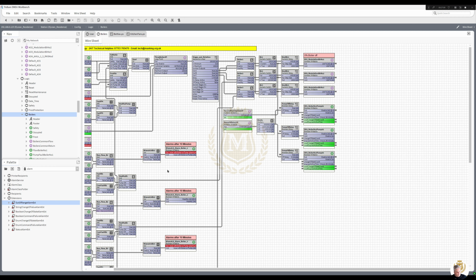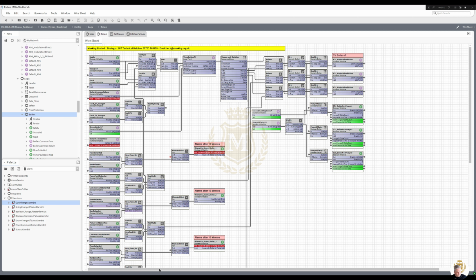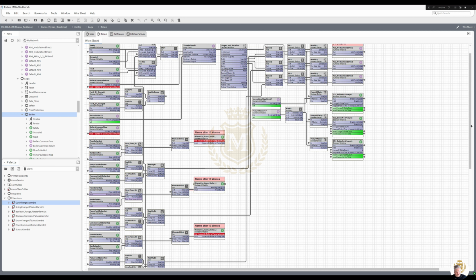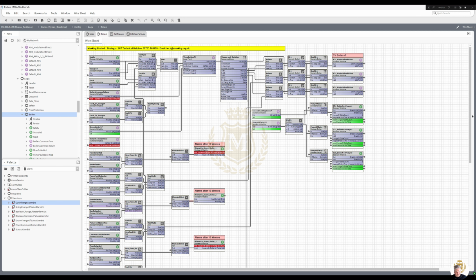And then of course I've got the other inputs. You can see that I've basically overridden the sensors there for these, hence that's why they're healthy, and I haven't overridden the sensors, that's why it's saying issue, and the alarms are there. We don't stop anything, we're just giving an alarm, and it's just for maintenance. That's all it's for. Even the temperature for the chilled water tank that we just done, cold water system, we're just sending it to maintenance and they will deal with it themselves. Again, you can pause this video and have a look, but it's quite basic. It's not really a lot of technical stuff here. In fact, it's zero technical stuff, but it's simple, does the job.